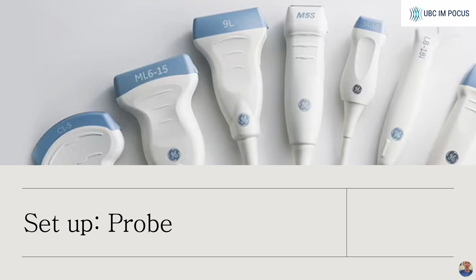However, the image in the superficial field is compromised. It is excellent for looking at moving structures, for example, the heart. It may be used in the abdomen and chest, however, the image quality generally is inferior to that of the curvilinear array transducer, especially in the superficial field. Next, the linear array transducer. It is seen here off the edge of the screen. It is a high-frequency transducer, providing excellent spatial resolution for superficial structures. The depth of penetration depends on the attenuation of surrounding tissue, but often starts degrading around 4 centimeters.